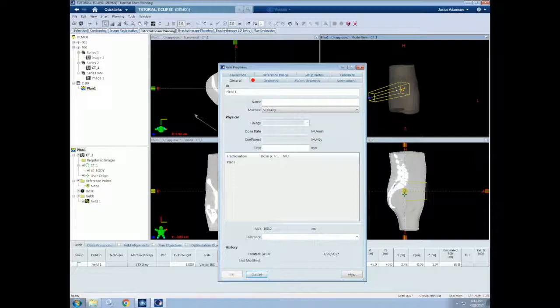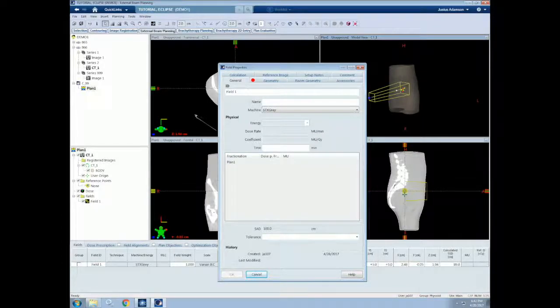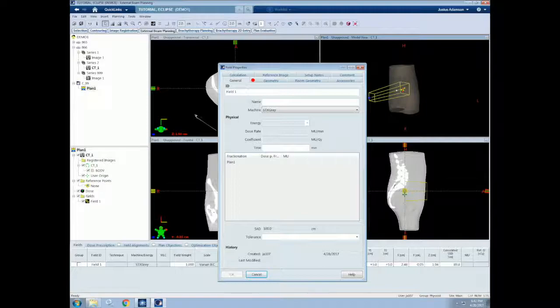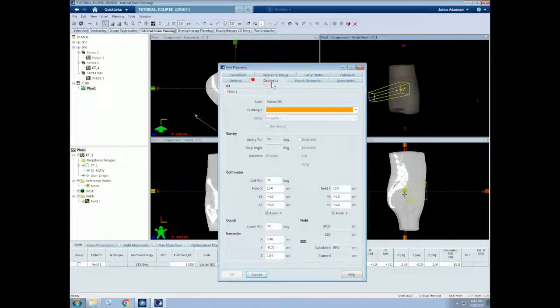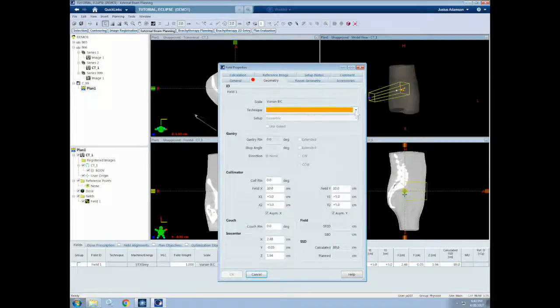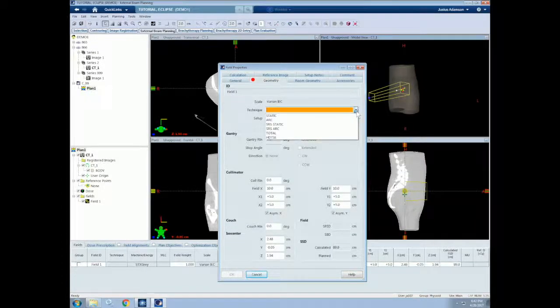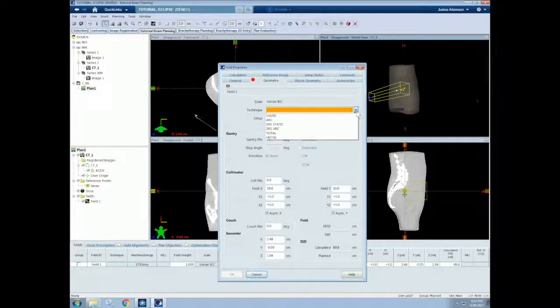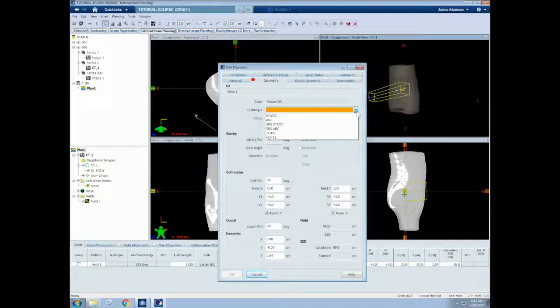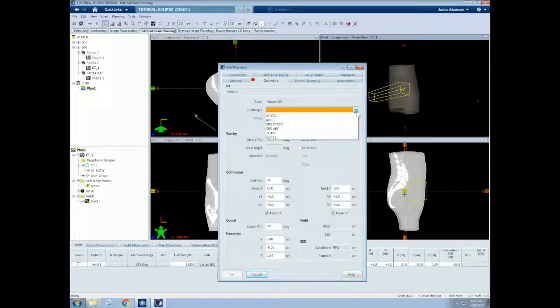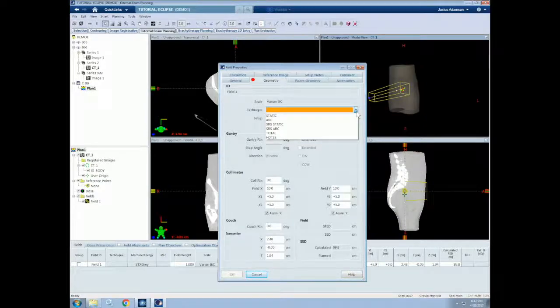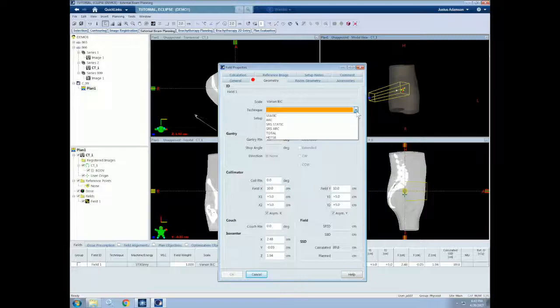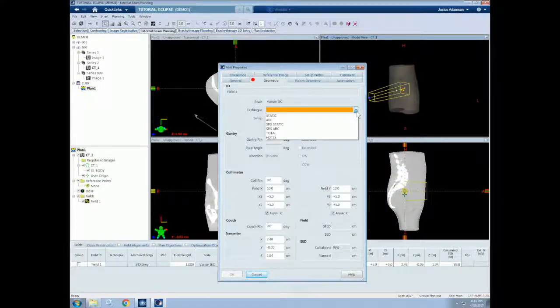Now there are some parameters that we must input before the beam can be created. A red dot, or orange highlighted area in the window, indicates required parameters that still need to be entered. Let's fill out these red dots until we have a completed beam. First, we must choose the technique. Depending on our technique, we may need to input more parameters before having an acceptable beam. We can select a static beam, an arc beam used for dynamic arcs and VMAT technique, or SRS beams. Specifying an SRS beam here allows the beam to have more total monitor units. Otherwise, it would require a manual override at the treatment console. It does not necessarily change the beam parameters.